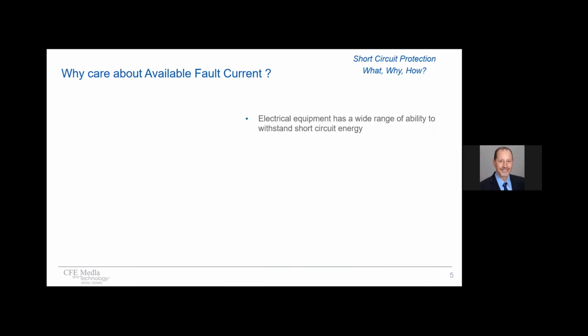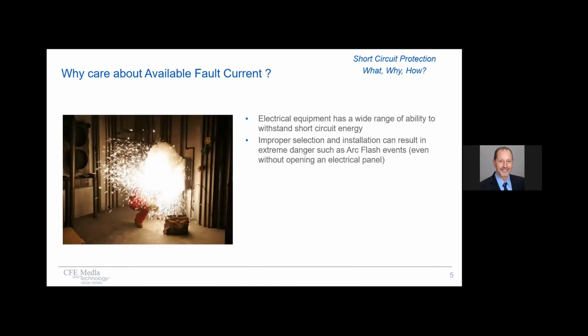Well, we care because, number one, electrical equipment has a wide range of ability to withstand short circuit energy. They're not all the same. Not all equipment is the same. Secondly, if there's improper selection somehow, it could result in a very dangerous situation known as arc flash. And even without opening an electrical panel, this can happen.